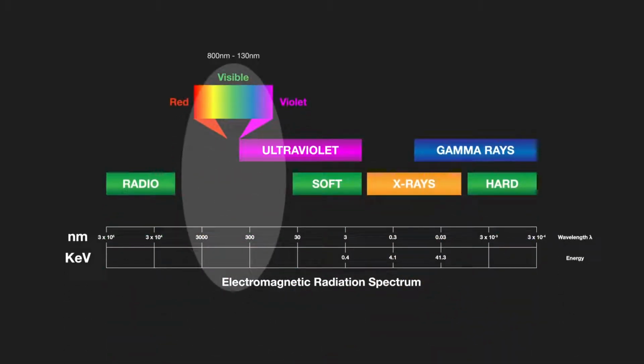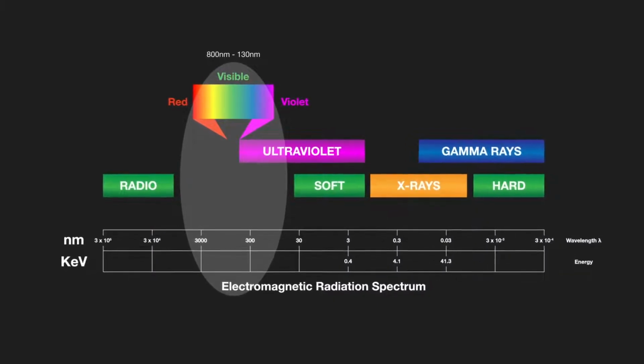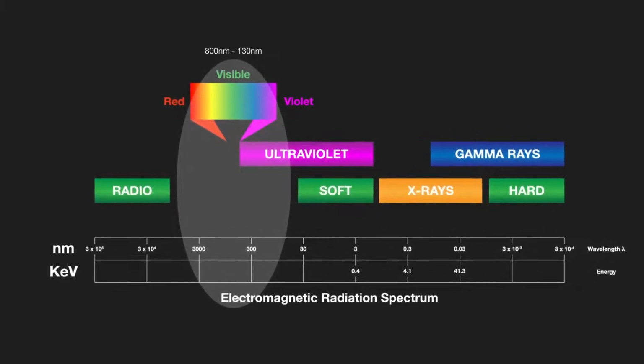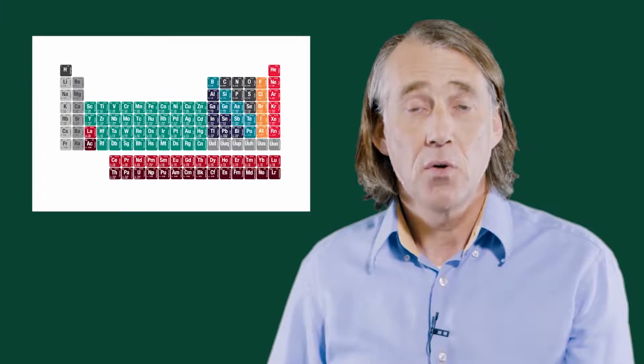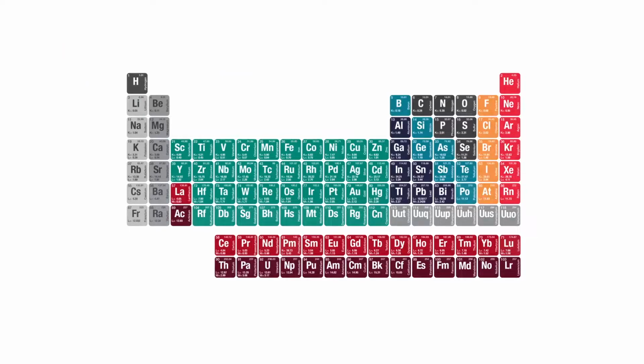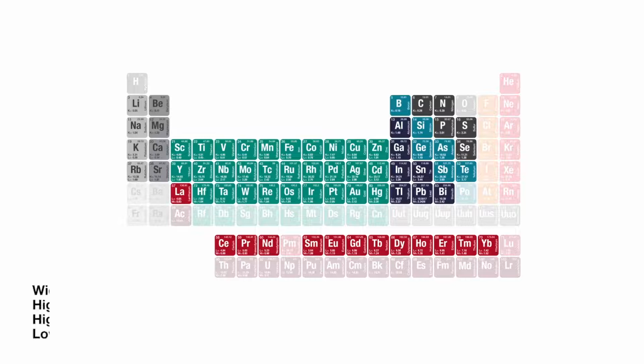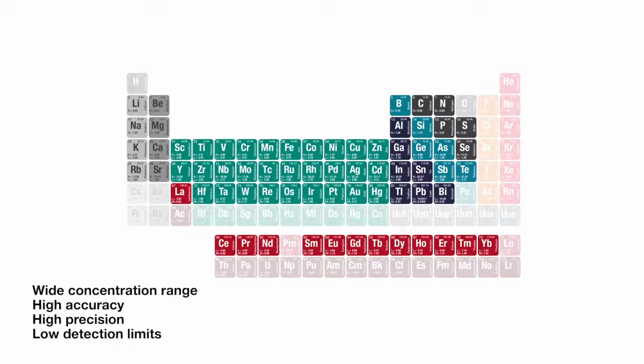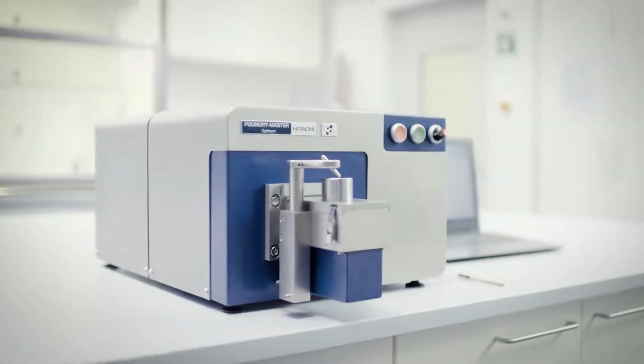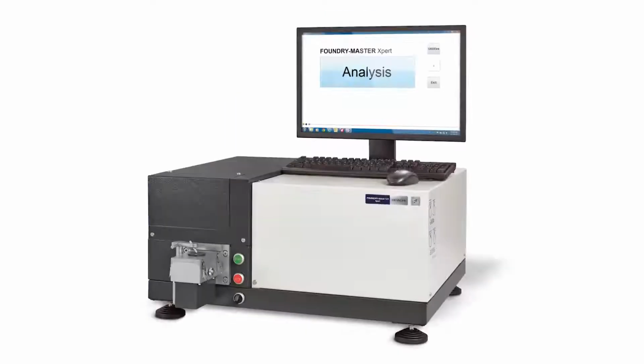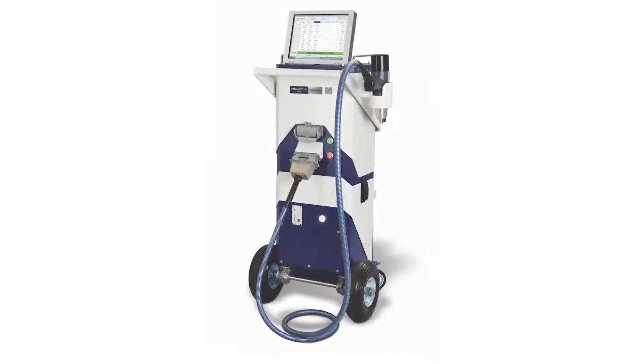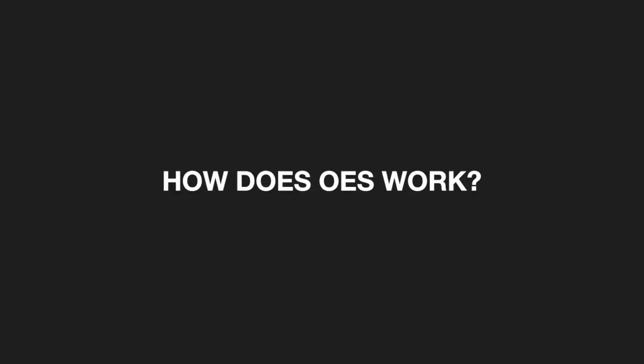The part of the electromagnetic spectrum which is used by OES includes the visible spectrum and part of the ultraviolet spectrum. In terms of wavelengths, that's from 130 nanometers up to around 800 nanometers. OES can analyze a wide range of elements from lithium to uranium in solid metal samples, covering a wide concentration range, giving very high accuracy, high precision and low detection limits. The elements and concentrations that OES analyzers can determine depend on the material being tested and the type of analyzer used. So how does optical emission spectroscopy work?